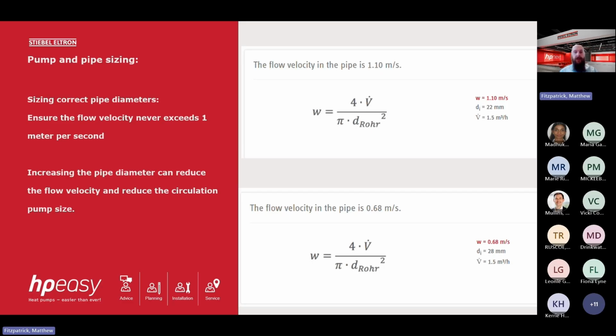So if we look at how we can counteract this and bring it below 1 meter per second, on the second example, we still only require 1.5 meters cubed per hour. But if we increase the pipe diameter to 28 millimeters, we now have a flow velocity of 0.68 meters per second, which is a lot quieter and a lot more efficient and effective for the system.